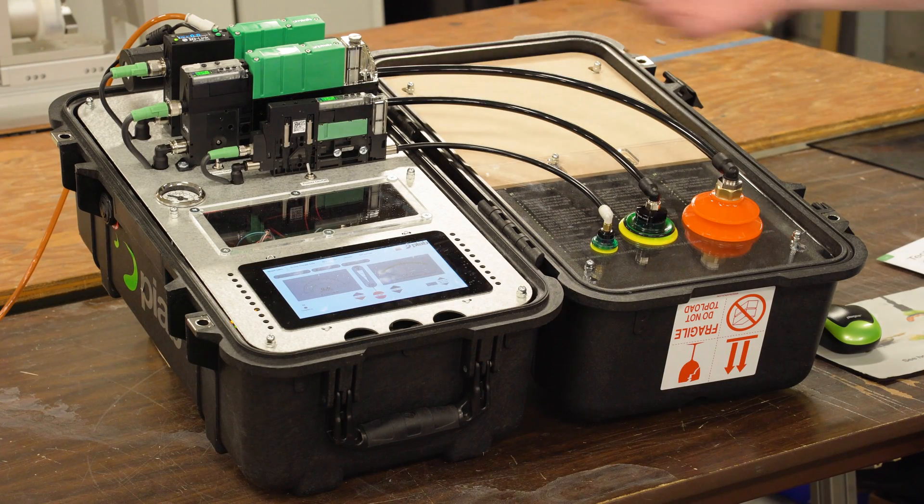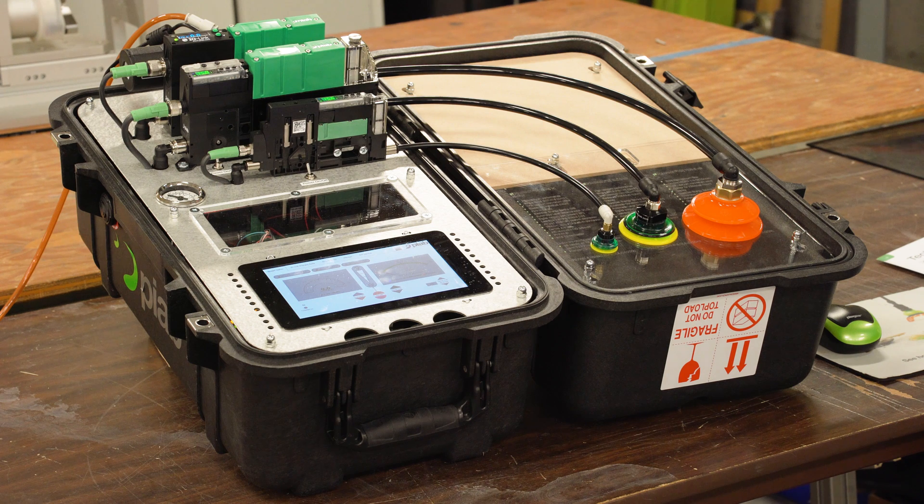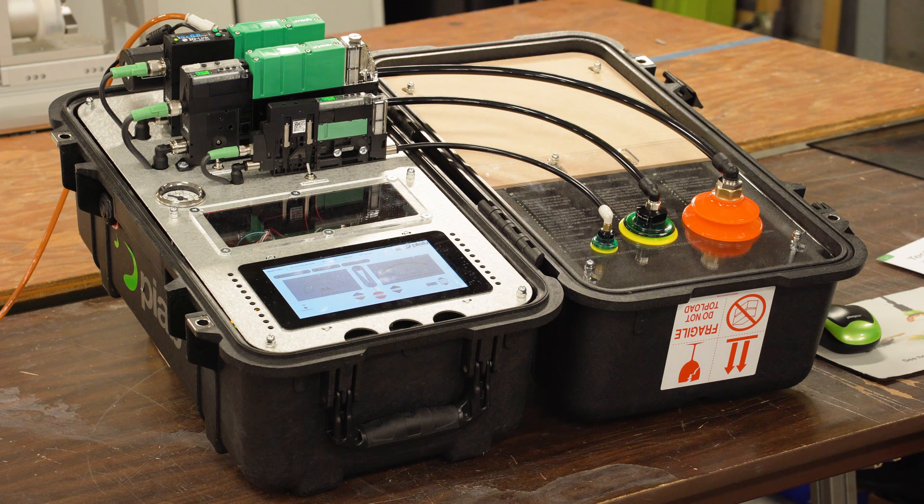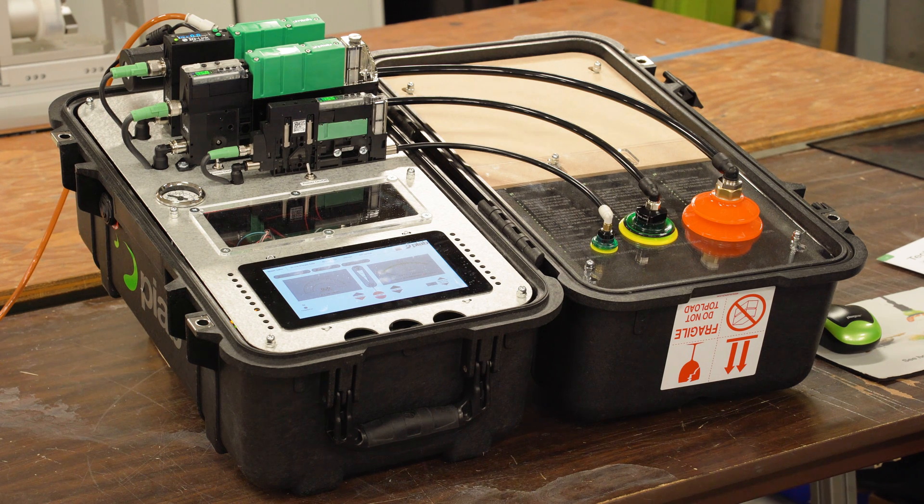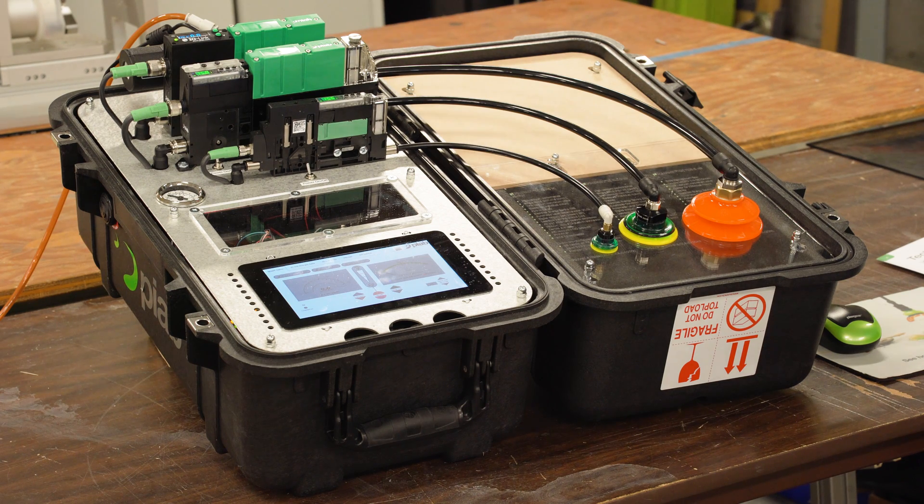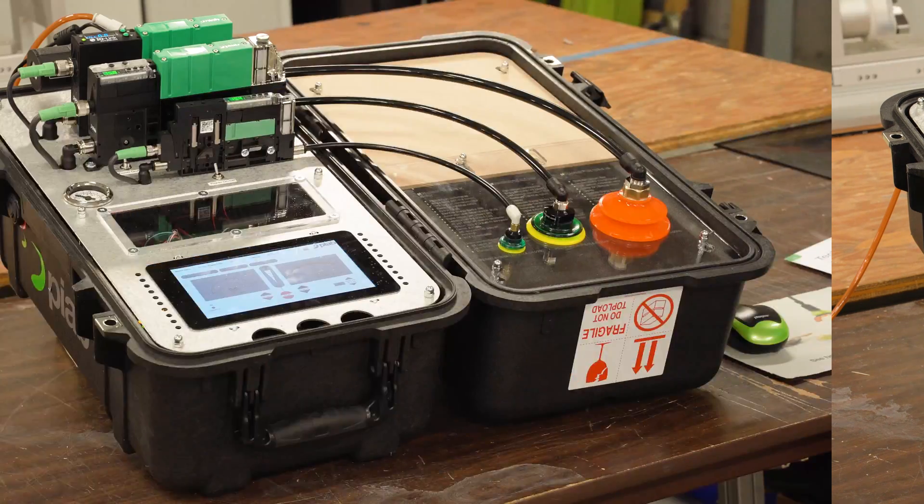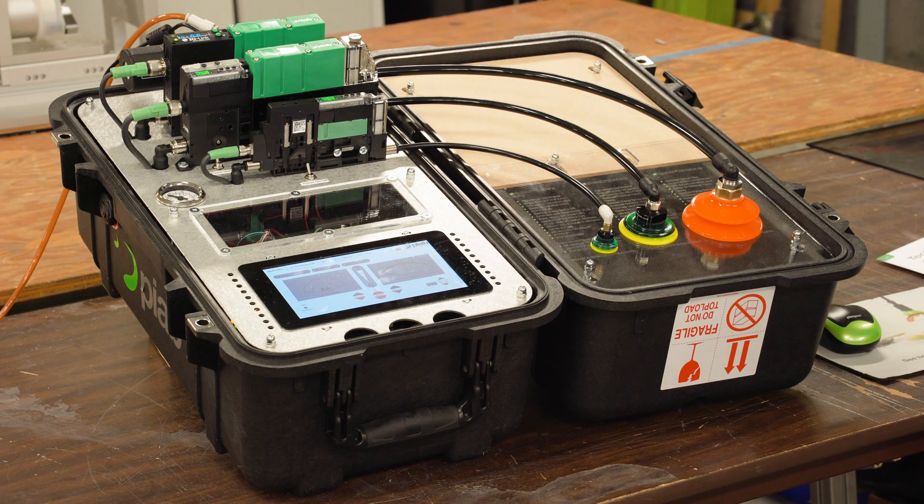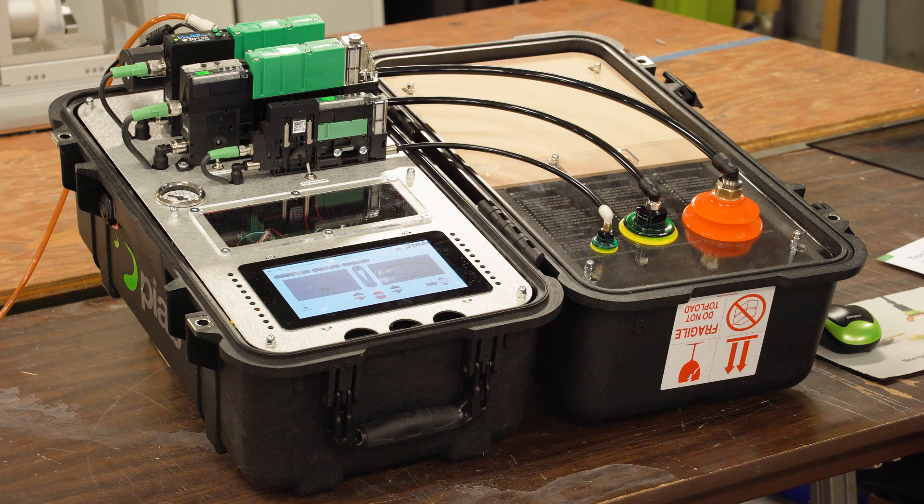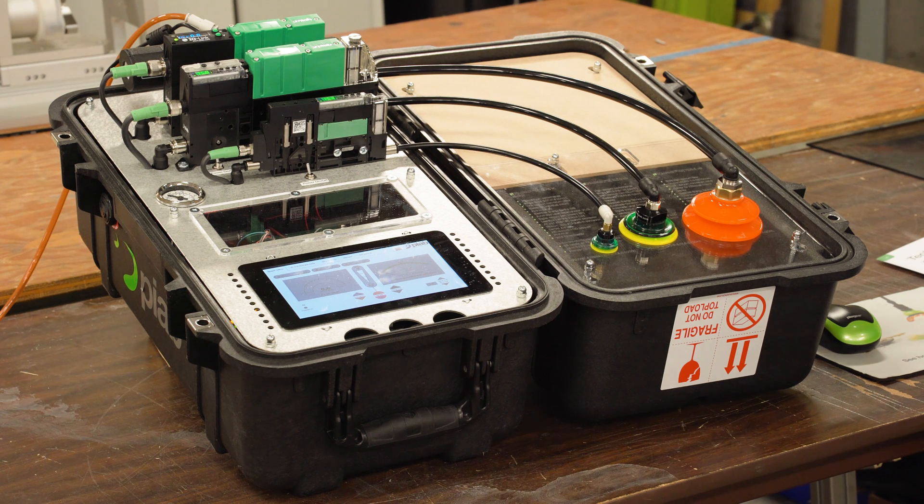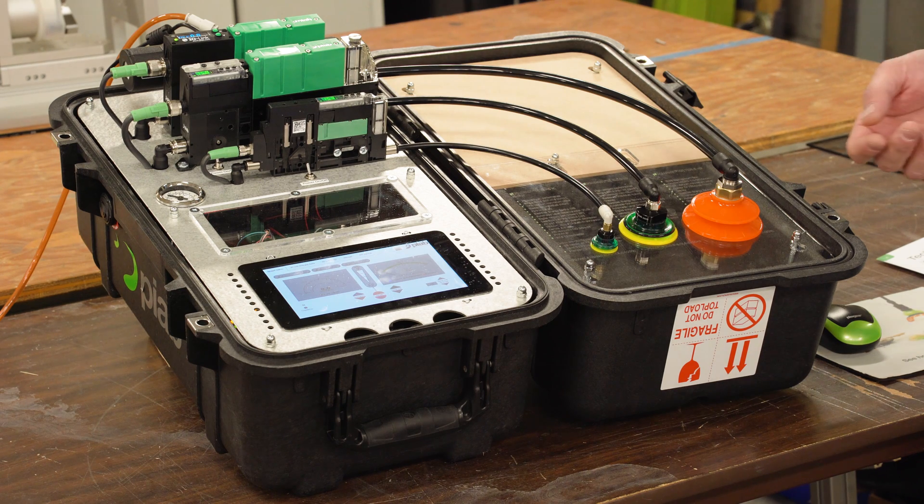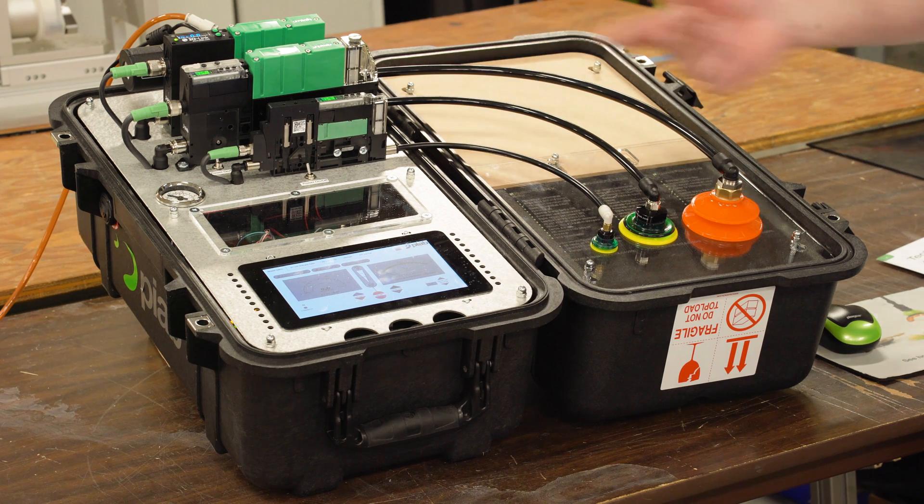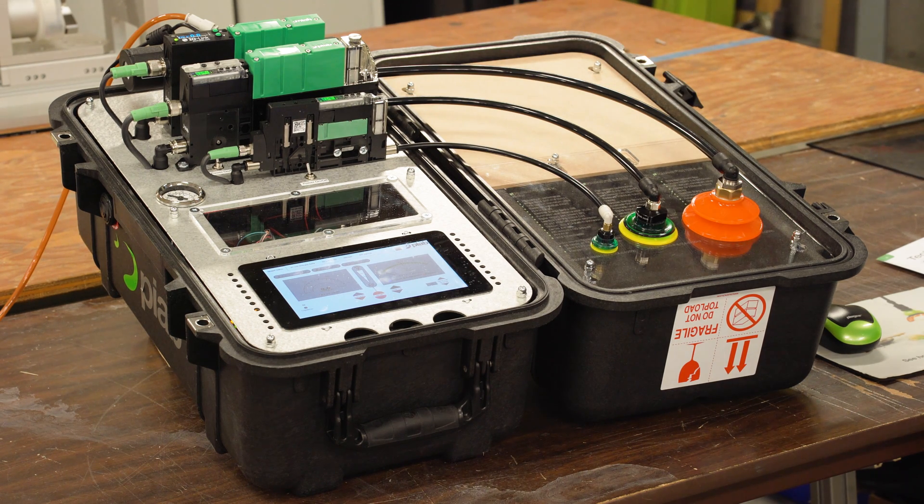So this is energy saving. We've got this set to where it reaches a certain value. Did you hear it purge? It pulses. As it leaks down, it'll reach a lower set value. It'll switch on, reaches the lower set value, it pulses, gets it back up to the high set value. And then there's a third set value, which is our switch output, which this one's not on. Somebody's messed with the setting, but we can change that real quick.